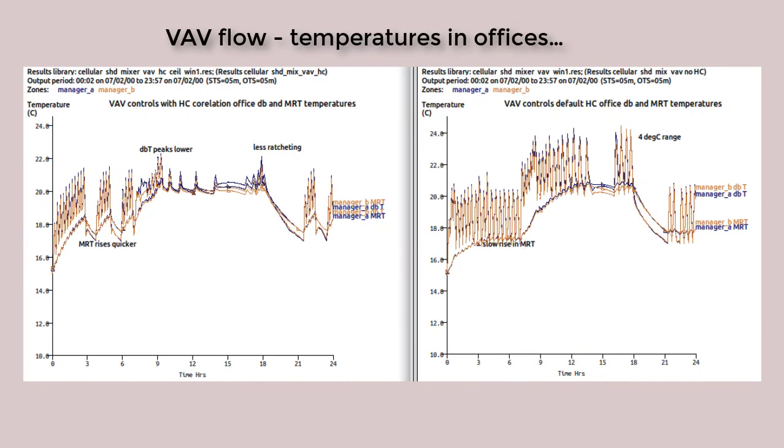Let's turn our attention to VAV flows in the offices. On the right we have the default initial model, on the left we have the model with the addition of heat transfer regime. The ratcheting is definitely, again, different. It takes much longer for the mean radiant temperature in the space. In the original case, that's actually maybe 2 o'clock in the afternoon before we reach a stable condition, whereas the stable conditions happen around 10 o'clock in the morning.